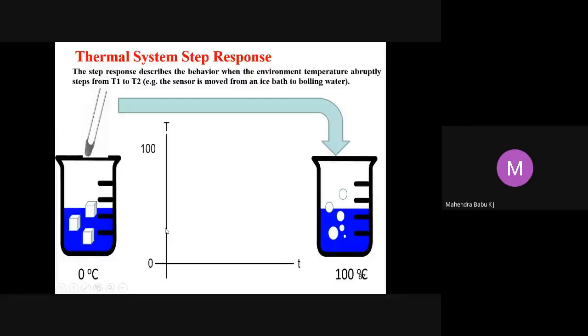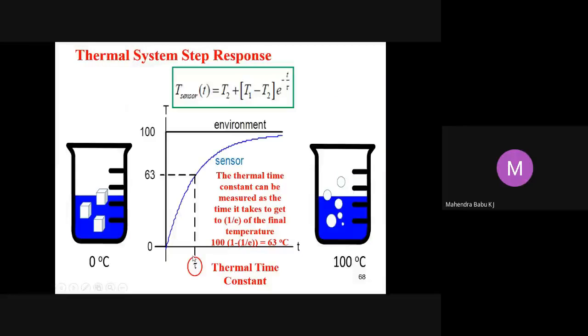Thermal system step response. As you know, the step response is one of the convenient and widely used indices for showing how fast a response can reach a steady state. So the thermal time constant is one of the indices used to show how fast a sensor can reach its steady state. This is the time it takes for a response to reach about 63% of the total response when the sensor undergoes a step change in its input. In practice, if the thermometer reaches 99% of the liquid temperature, it can be considered to have reached the steady state value. This occurs at about t equal to 5 times tau, that is, the thermal time constant. So here you can see the response curve.